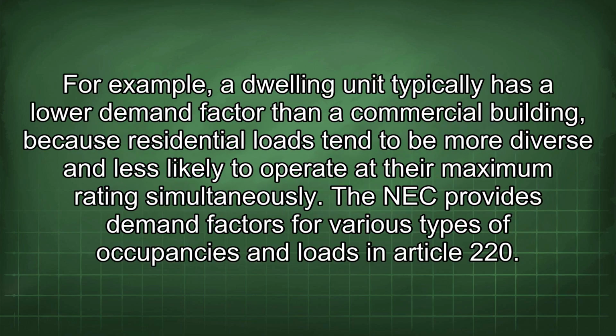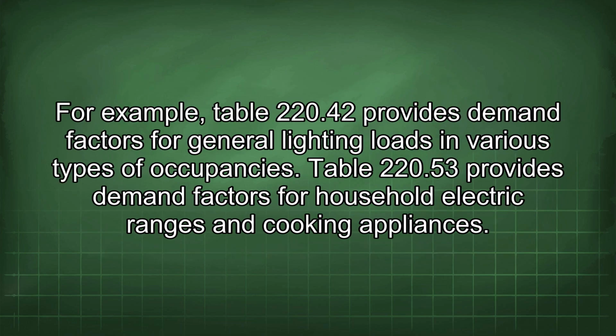For example, a dwelling unit typically has a lower demand factor than a commercial building, because residential loads tend to be more diverse and less likely to operate at their maximum ratings simultaneously. The NEC provides demand factors for various types of occupancies and loads in Article 220. For example, Table 220.42 provides demand factors for general lighting loads in various types of occupancies. Table 220.53 provides demand factors for household electric ranges and cooking appliances.